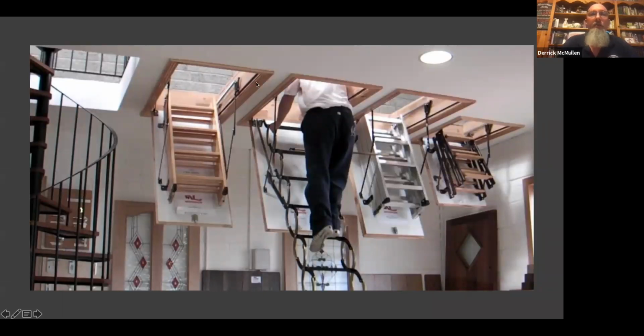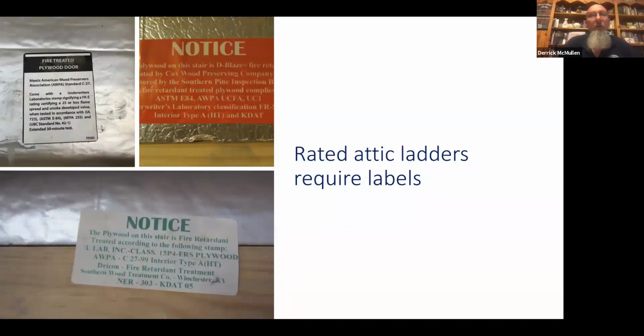That would be if there were gaps there, you go in there and they just throw this up and they don't put anything here, they don't caulk around it, they don't seal it. That's an annular space that was not filled. So yes, it has to be filled. I think somebody just asked that question just a few minutes ago.